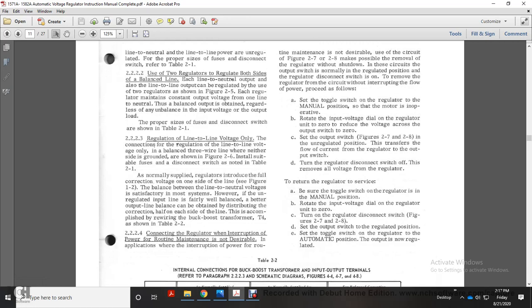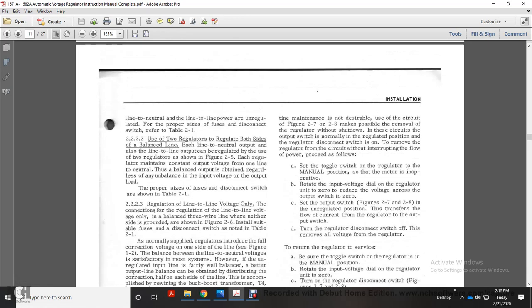Alright, 2.2.2.4, connecting the regulator where interruption of power for routine maintenance is not desirable. In applications where the interruption of the power for routine maintenance is not desirable, use the circuits in Figures 2.7 and 2.8, which make possible the removal of the regulator without shutdown. These circuits have the output switch normally in the regulated position with the regulator disconnect switches on. To remove the regulator from the circuit without interrupting the flow of power, proceed as follows.